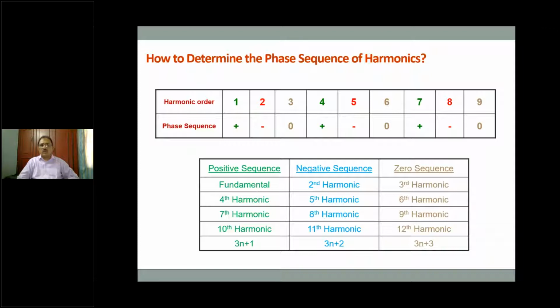These are caused by single phase loads with 2 or 4 diodes. And in a typical application, all these triplen harmonics, or zero sequence harmonics, will club together and typically flow through the neutral. Some of you who are electrical will now understand why the National Building Code specifically called for, instead of TPN, equal size or even 2 times larger size for the neutral. Since the incidence of harmonics has increased because of nonlinear loads, people have been using 2 times the conductor size for neutral, while the R, Y, B phases, the 3 phases, are normal size. The reason is the flow of unbalanced current through the neutral.